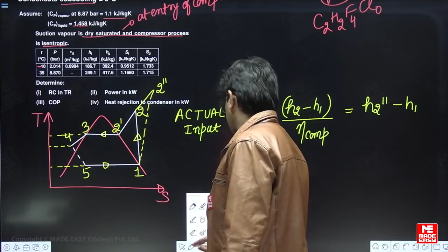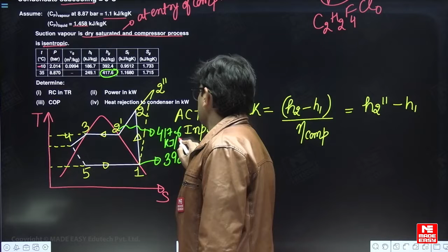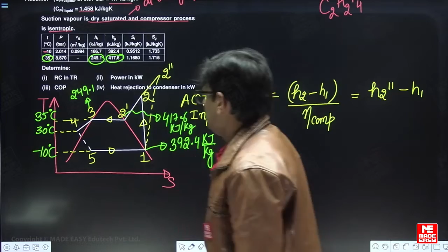At minus 10 degrees Celsius, the value is 392.4 kilojoule per kg. Now H2 dash, corresponding to 35 degrees Celsius, is 417.6 kilojoule per kg. H3 is corresponding to 35 degrees Celsius, and that is liquid, so it is 249.1. This is corresponding to 35 degrees Celsius, and this is corresponding to minus 10 degrees Celsius. One more thing: in this case subcooling is mentioned, the condensate subcooling is 5 degrees Celsius, so we can say this temperature is 30 degrees Celsius.